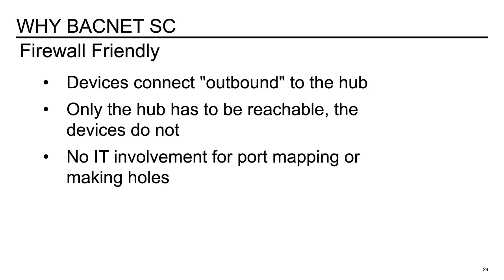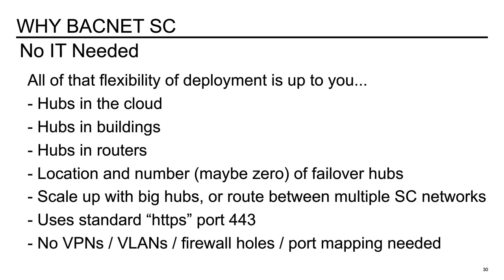So with BACnet SC, no IT is needed. The deployment and the flexibility that you use is up to you. You can have hubs in the cloud. And when I say hubs, the primary hubs and failover hubs, you can have them in buildings. You can have them in routers. The location and number of failover hubs, and like I said, you could have 0, they are not required. You can scale up with big hubs or route between multiple SC networks. So this makes BACnet SC very scalable.